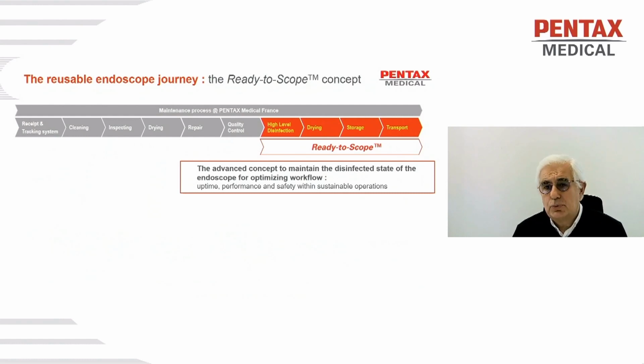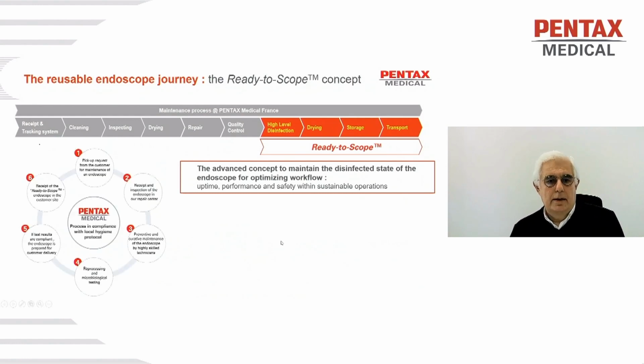So what we created in France is a scheme called Ready to Scope, where we take care internally of the burden of making sure the scope is in a perfect bacteriological state to go into the exam room. And how is the process working? First, the entire process: we pick up the endoscope from the customer, we inspect it, we repair it with our technician, and when the repair is done, we reprocess and we do the microbiological testing. Then, if the test is compliant, we dress the endoscope.